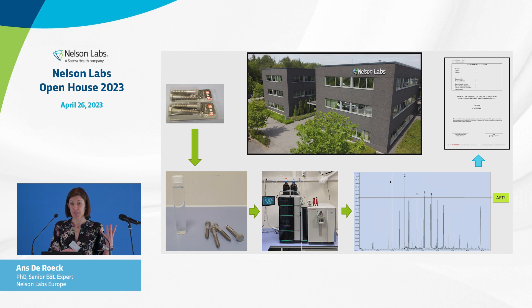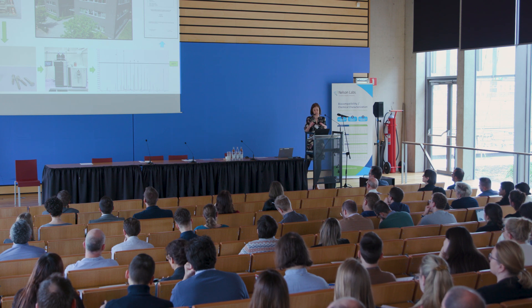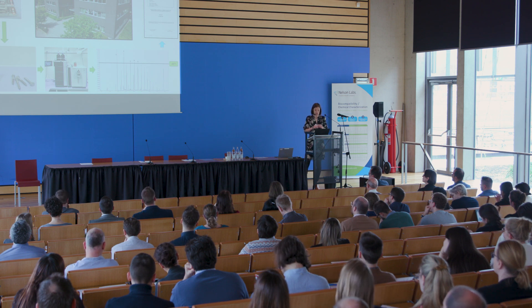Our input is a medical device, output is a report containing the compounds and concentrations that can migrate from the device. The first step is that we make an extract of the medical device; this extract is subsequently analyzed by different techniques. We obtain a chromatogram, apply a threshold, and all compounds above this threshold need to be identified and quantified. My talk covers the first step ending with a chromatogram; the subsequent speakers will cover the last part.